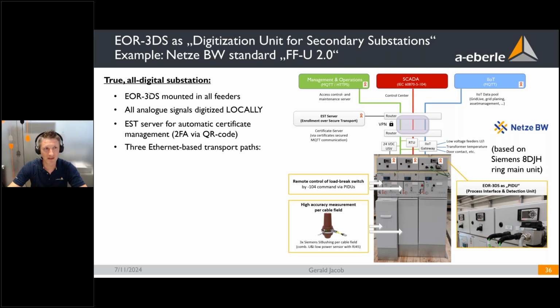I wrote in here true all digital substations. So what does it mean? The EOR3DS is mounted really in every single feeder, also in the transformer field. This is interesting because in the transformer field there is no measurement installed. So the EOR3DS in the transformer field is really only used for the digitization of 6 binary inputs: of the load breaking switch, the earthing switch, and 2 further items of information. One of them is the gas alarm of the whole station.